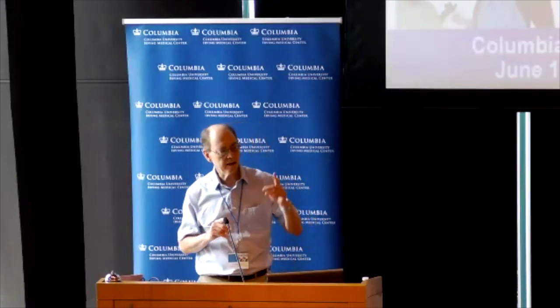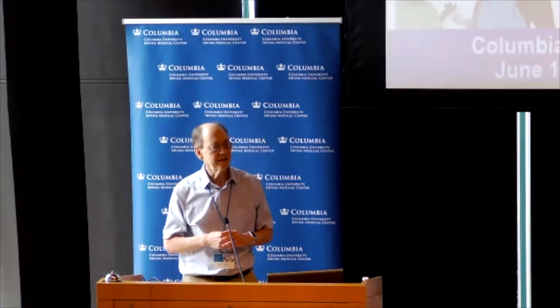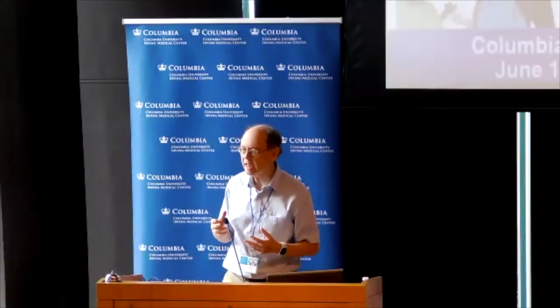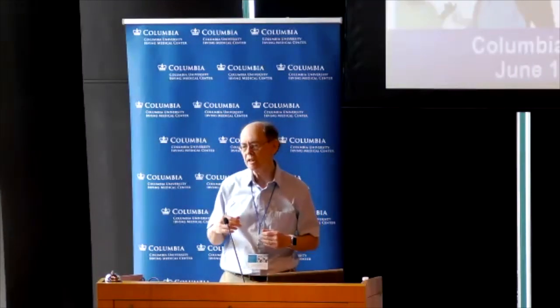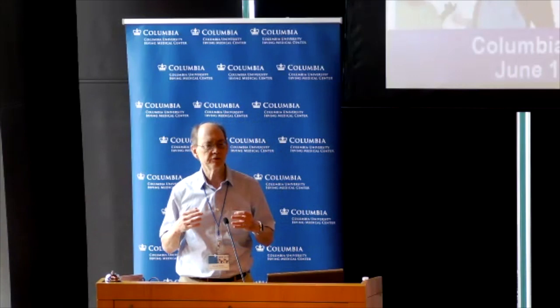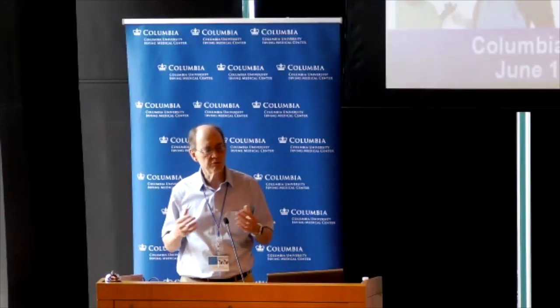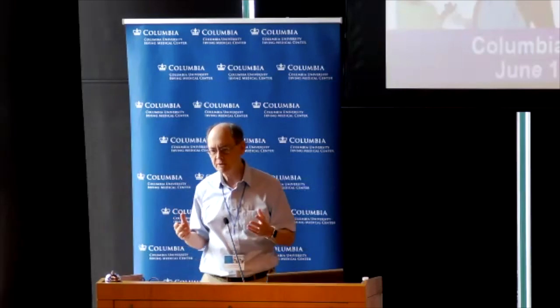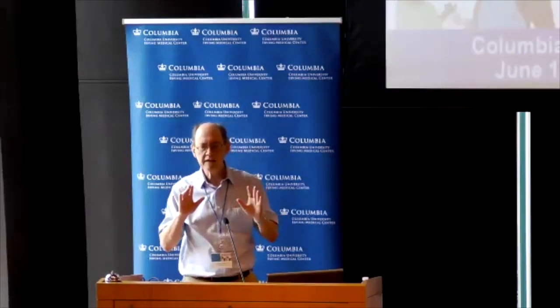And Ed had a paper a decade or so ago showing that with upper room UV, with actual dose measurements, people's exposures in the rooms were a small fraction of what the irradiance measurements would give you. And so it's important not to confuse these things.